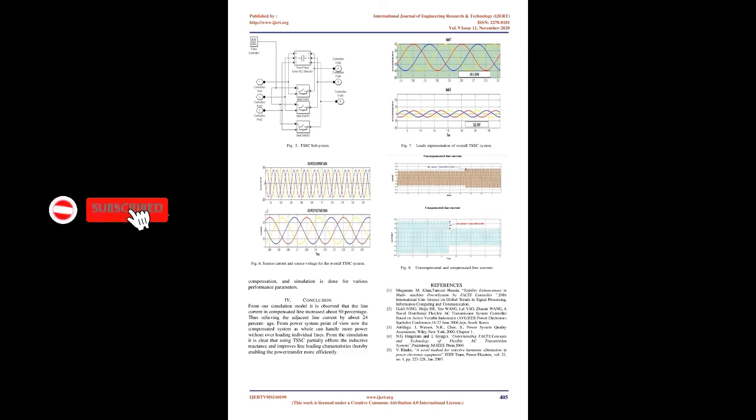in such a way that its phasor Vc is in quadrature with line current I, this series compensator neither supplies nor absorbs active power. As previously discussed, power at the series source is only reactive and the voltage source may, in this particular case, be replaced by a capacitive or inductive equivalent impedance. The equivalent impedance would then be given by Zeq = XL(1 - s), where s = Xcomp/XL, and s is the compensation factor, and Xcomp is the series equivalent compensation reactance, negative if capacitive and positive if inductive. In this case the compensation voltage is given by Vc = I·Zeq and the transmitted power is equal to Ps = V²/(XL(1 - s)) sin δ.